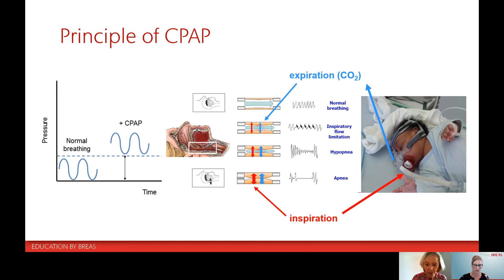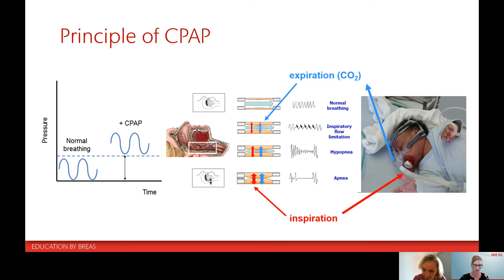The aim of CPAP is to open the airway by delivering a constant pressure through the entire breathing cycle. You can see on the figure on the left normal breathing, and here the normal breathing of a child above a certain positive airway pressure which is necessary to maintain the airways open. It is a very simple mode of ventilation with a constant airflow and a calibrated leak to allow the exhalation of expired carbon dioxide during expiration.